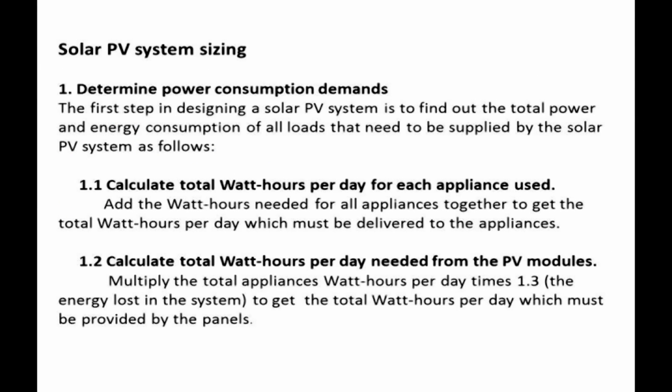Solar PV system sizing. Step 1: Determine power consumption demands. The first step in designing a solar PV system is to find out the total power and energy consumption of all loads that need to be supplied by the system. Step 1.1: Calculate total watt-hours per day for each appliance used, then add the watt-hours needed for all appliances together to get the total watt-hours per day which must be delivered to the appliances.